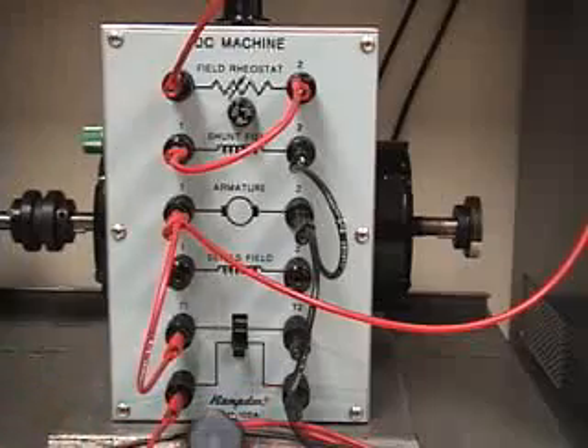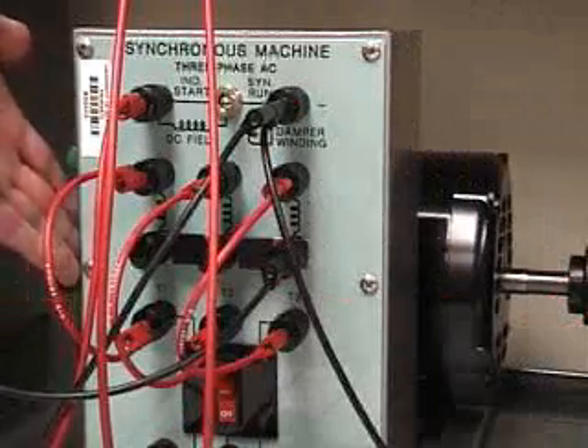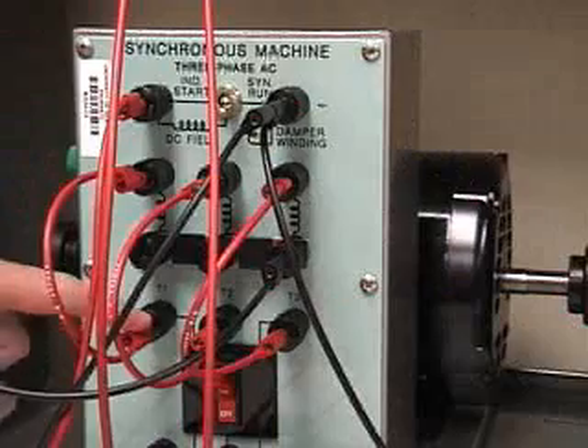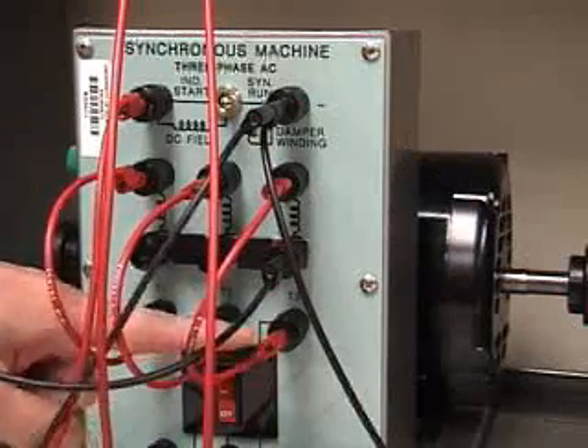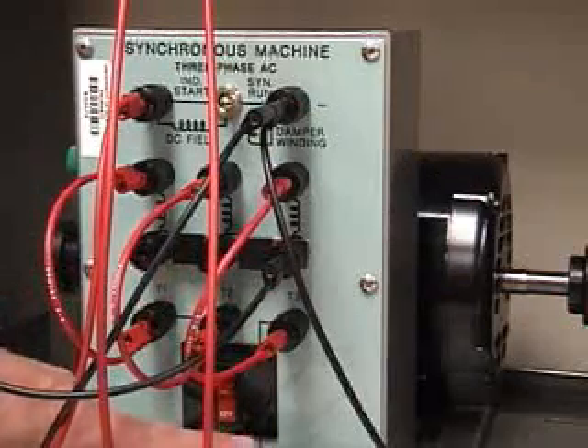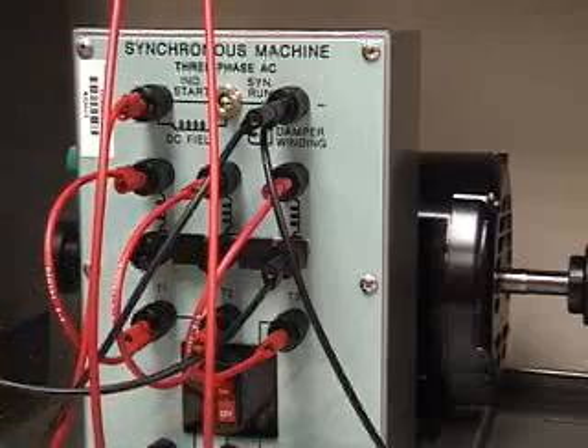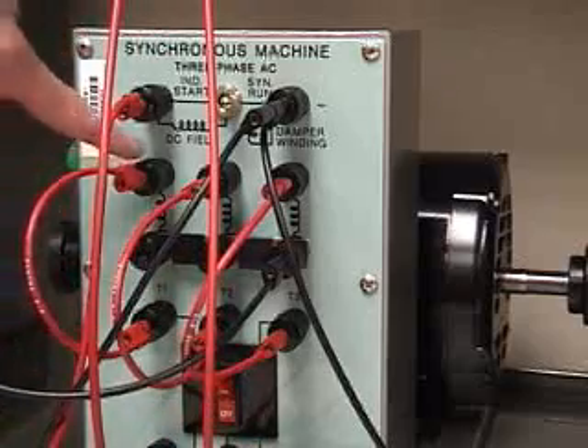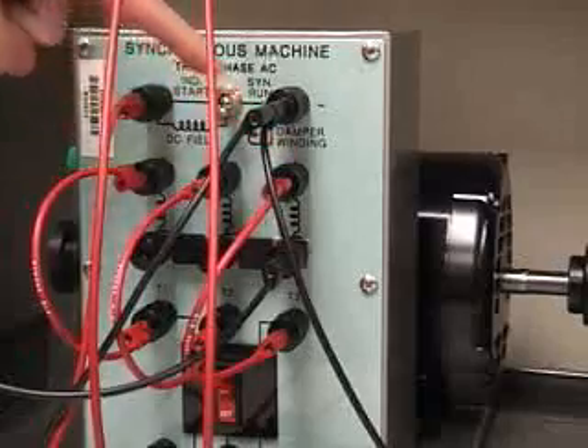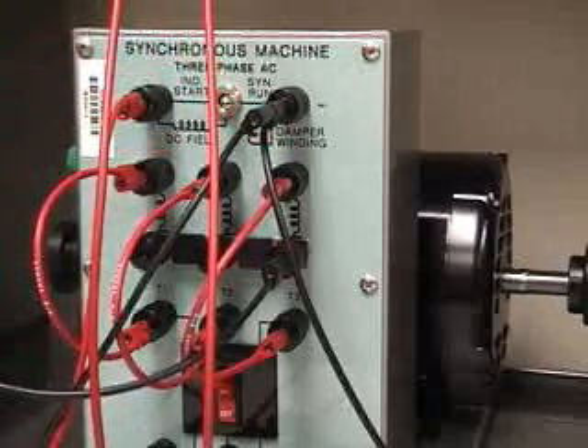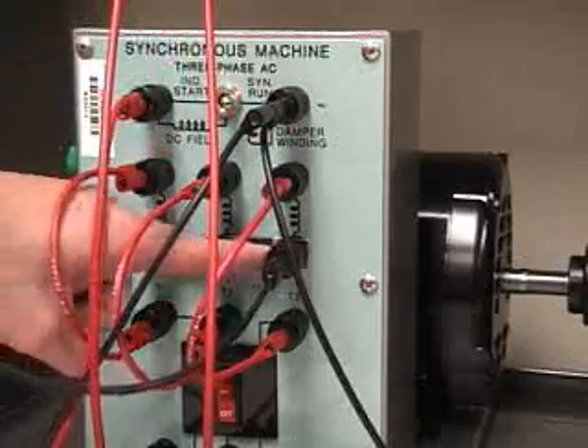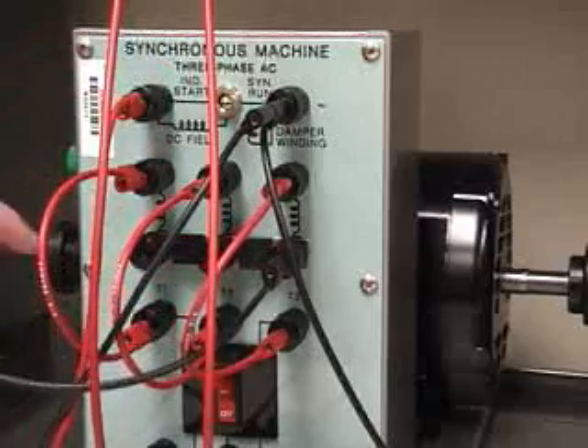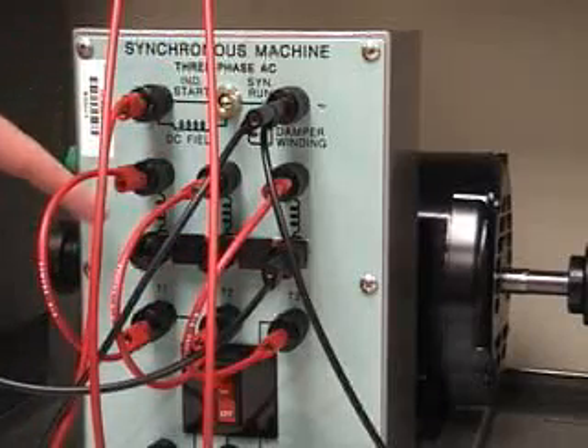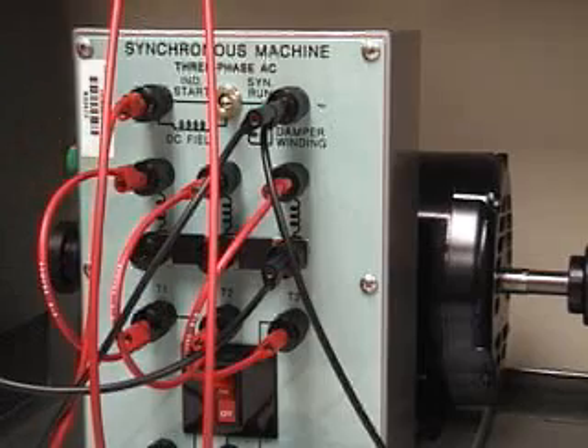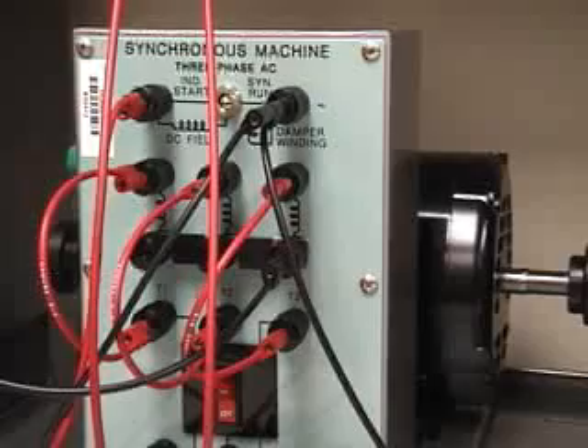On the synchronous machine, configured as a motor, our ABC three phases are input here from the load side or source side of the circuit breaker, and from there we jump them up to the three windings on the stator of the machine. One side of the windings is tied together, which goes back to the source neutral, which makes this a Y-connected three-phase motor. Also very important in a synchronous machine is the excitation winding or field winding.